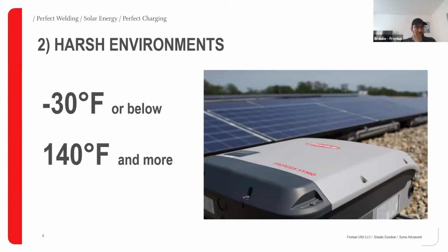Another challenge we're seeing is that mounting inverters on the rooftop is a big consideration, because being on the roof means the inverters go through very harsh environments. In places like the Midwest, winter polar vortexes can drop temperatures all the way to -30 or even below. In places like Arizona, Southern California, or Texas, it can get really hot in summer, with temperatures going up to 140 degrees and more. By their nature, flat rooftops on commercial buildings are pretty harsh, whether in summer or winter.